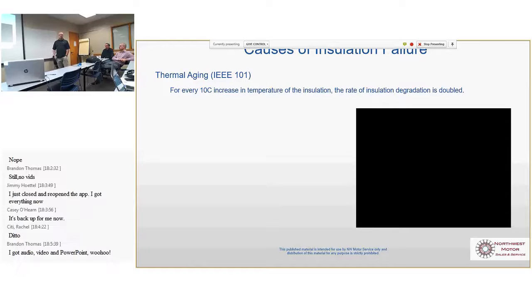Talking about the thermal aging. I think Ed touched on this also, but for every 10 degrees Celsius rise in temperature, the insulation degrades - the insulation life gets cut in half. That's what it's all about. Yeah, that's how they preach it in a lot of different schools you go to, so it's a big deal. Sounds kind of crazy, but it's true.